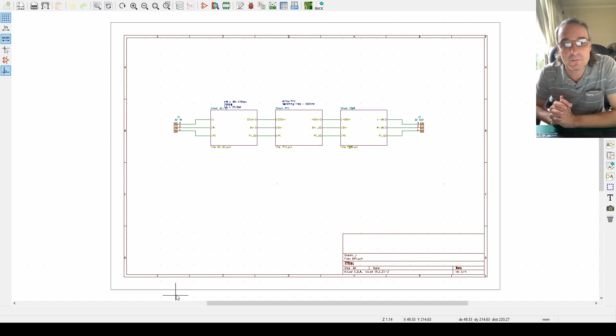I would have preferred to take the control voltage, rectify it, create a DC bus. This is all straightforward, you would find this in any sort of drive circuitry or anything like that. Then on the DC bus we put a whole bunch of capacitance, and then we invert it. That way we can control the output voltage level as well. So we have a true full online inverter, dip-proof inverter. And the point of controlling the output voltage would be so that we can keep it constant. So whatever noise, transient bullshit is coming through on the input, you will take out, and you will have a nice pure sine wave on the output.